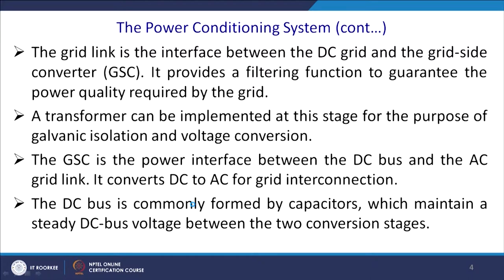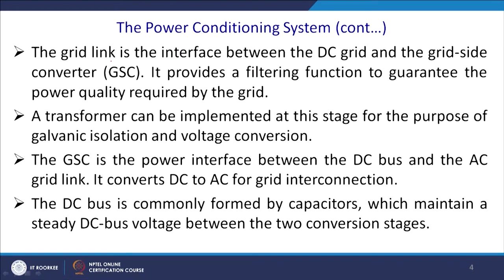The MPPT voltage depends on the string length, generating some DC voltage level. However, your DC bus may be connected to, say, 48 volts, and for this reason you require another DC-to-DC converter — your PVSC. Similarly, if you are injecting power to the grid, you require AC-to-DC and DC-to-AC conversion, named the grid side converter. The grid link, which is the interface between the DC grid and the grid side converter, provides filtering to guarantee the power quality as required by the grid code.